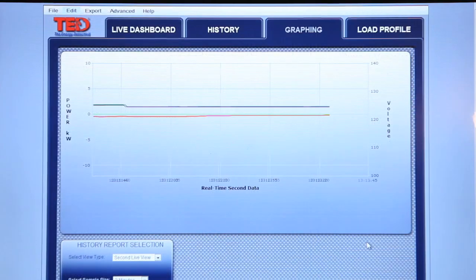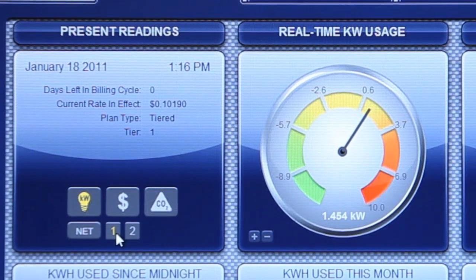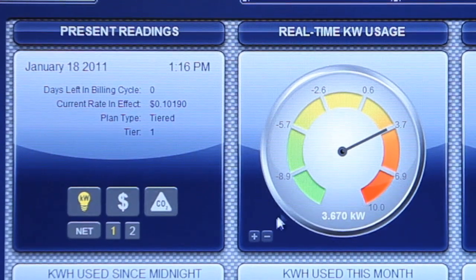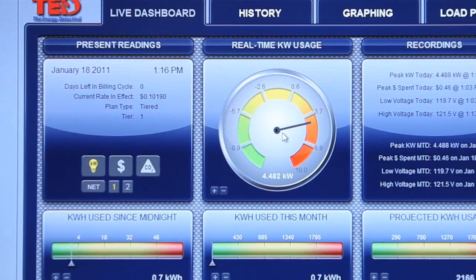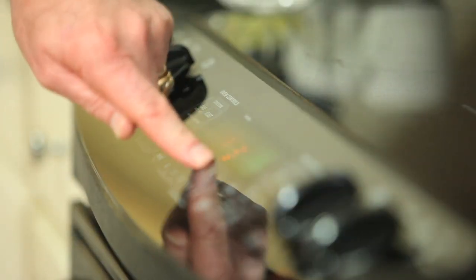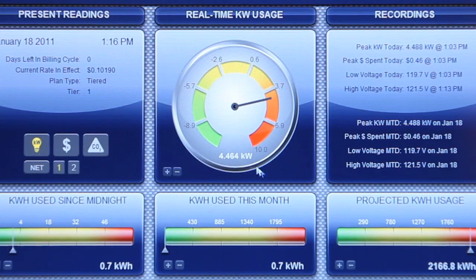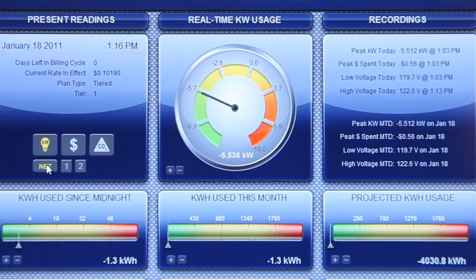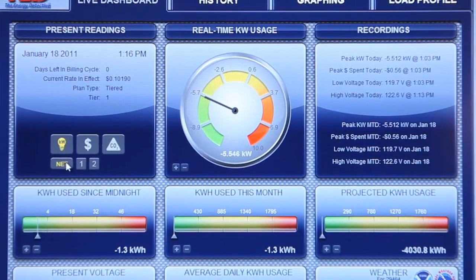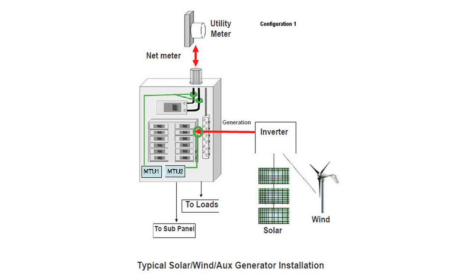This will allow the real-time dial and the graphing page to display a negative reading. With this configuration, clicking on MTU 1 will display the calculated value of the load in your home. Selecting net will show the amount of energy being pulled from or sent to the electrical grid. As a quick test of your setup, turn on a heavy load. MTU 1 will show this load as a positive number. The net button will reflect the amount of generation and the load in the home — with a large amount of generation this becomes negative, and with little generation this number becomes positive. If any of these readings are not as expected, check the polarity dots on the CTs and which IDs are assigned to each MTU.